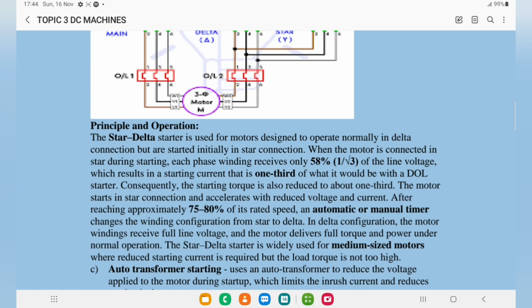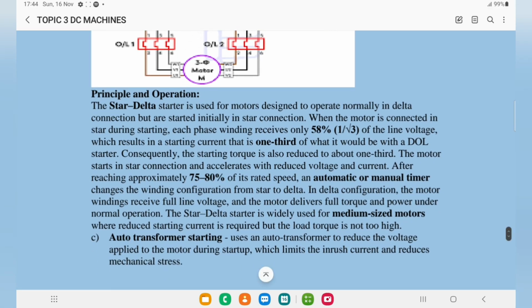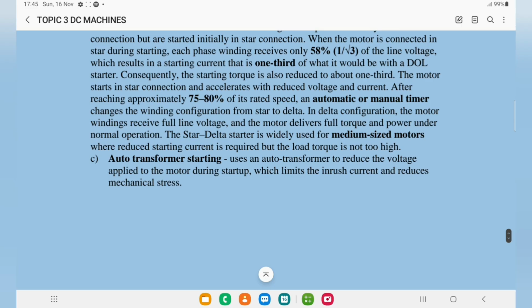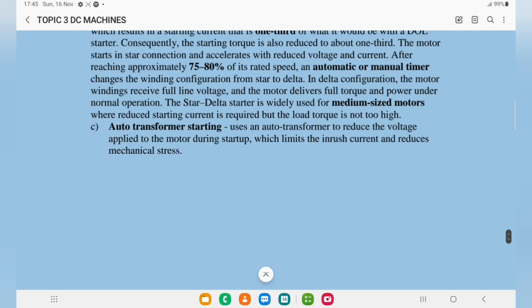An automatic or manual timer changes the winding configuration from star to delta. In the delta configuration the motor windings receive the full line voltage, and the motor is able to deliver its full torque and power under normal operation. You can be asked about the applications of this. You can just say that they are used in medium-sized motors where reduced starting current is required, but the load torque is not too high.